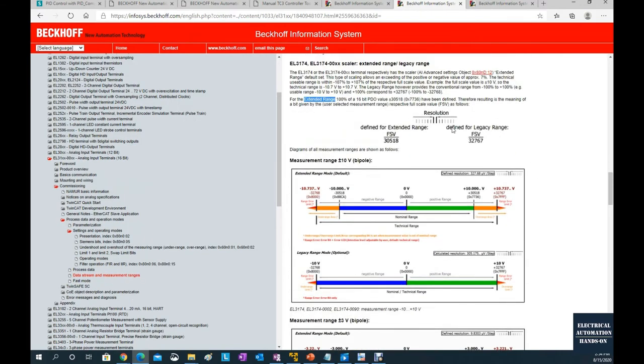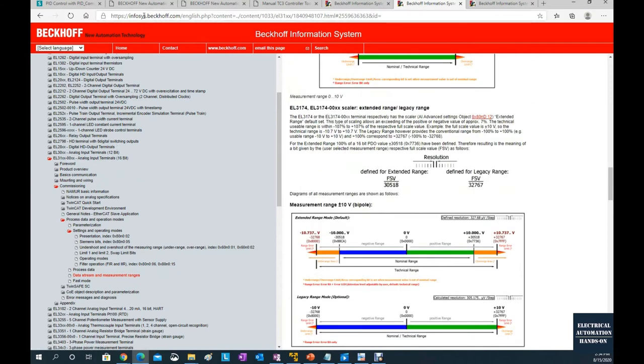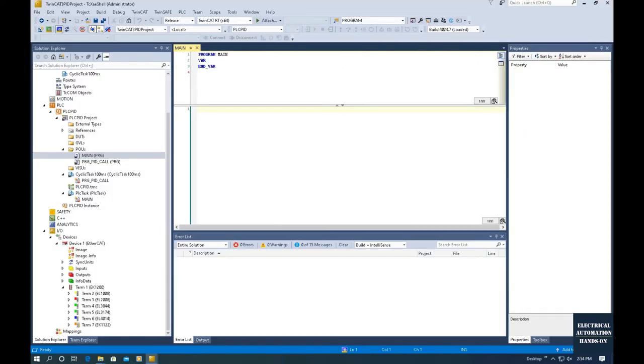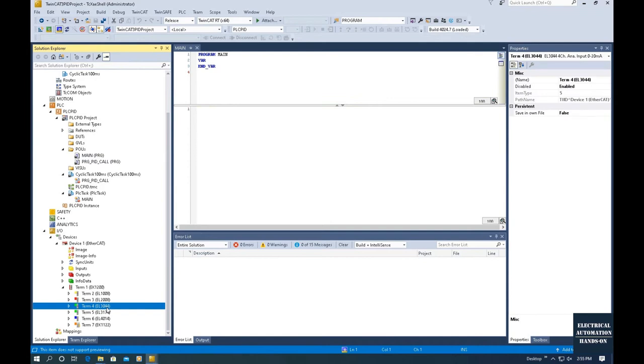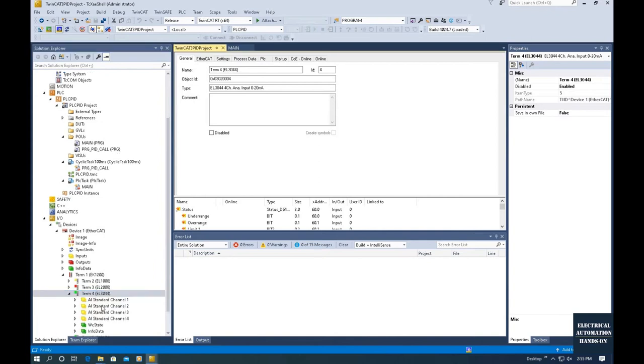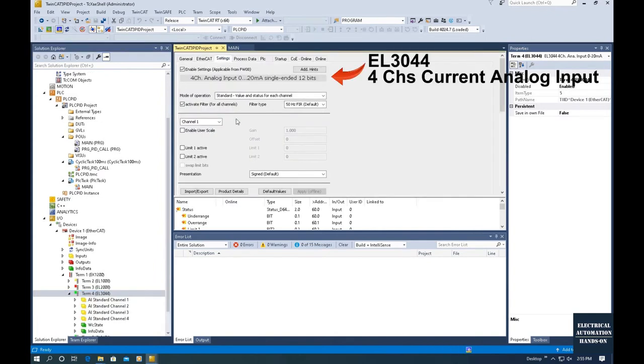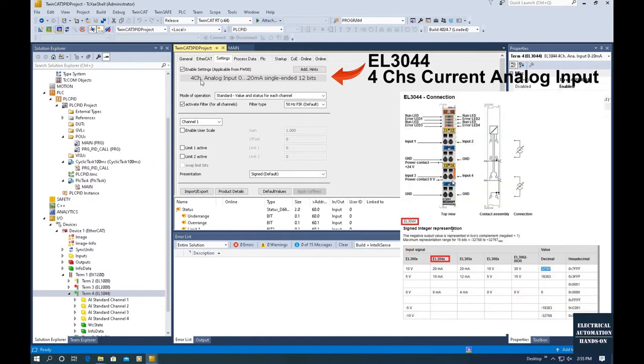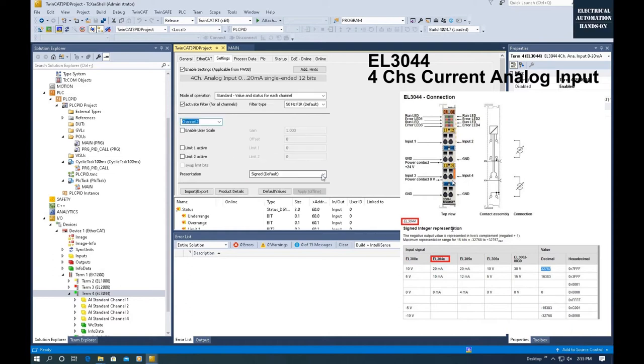I will mention this again when discussing the hardware configuration of this analog card. This page is from infosys.beckhoff.com under analog input terminals — data stream and measurement ranges. Back in the TwinCAT 3 project, the EL3044 is the current card. Double-clicking the card and going to settings, we can see it is a 4-channel analog input, 0-20mA. For each channel, you can select signed or unsigned. When this channel receives 20mA, the full range decimal value is 32767. You can also select a different filter if your channel has noise.